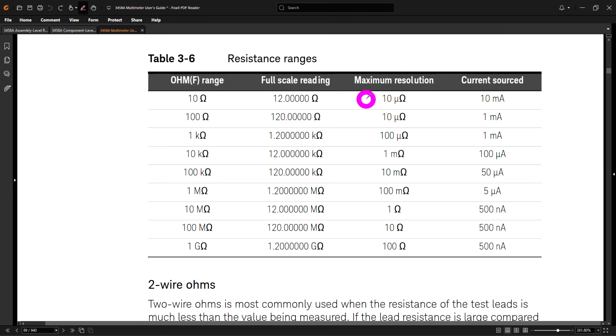So the 3458A has a very good resistance range measurement capability. When it is set to a 10 ohm range, it can measure resolutions down to 10 microohm thanks to its very high resolution internal A to D converter. And part of the reason for that is because when you're measuring a very small resistance, it pushes a fairly high current through it, 10 milliamp. Now 10 milliamp through 10 ohm is 100 millivolt, and that's more than enough to achieve this resolution of 10 microohm. But when you're doing a 1 gigaohm measurement range, you obviously cannot move 10 milliamp through that resistor anymore. You will have an enormous voltage. In that situation, the current is reduced to 500 nanoamp.